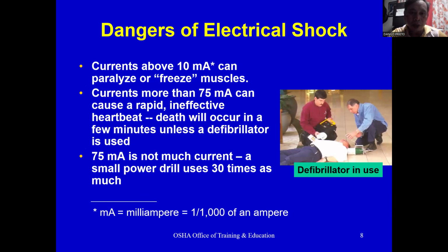Dangers of electrical shock. You have here an example also of a picture. Currents above 10 milliamperes can paralyze or freeze muscles. Currents of more than 75 milliamperes can cause a rapid and ineffective heartbeat. Death will occur in a few minutes unless a defibrillator is used. 75 milliamperes is not much current. A small power drill uses 30 times as much.